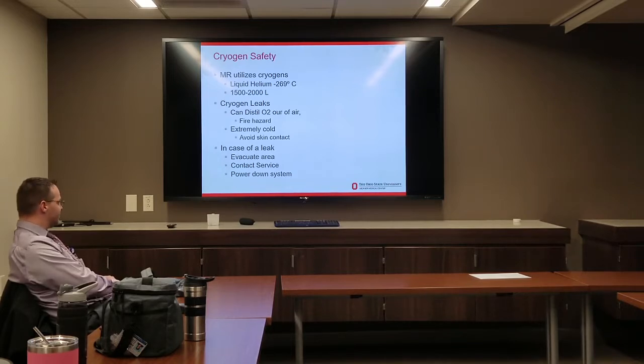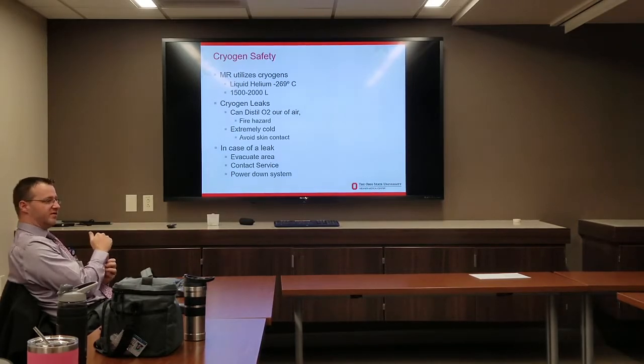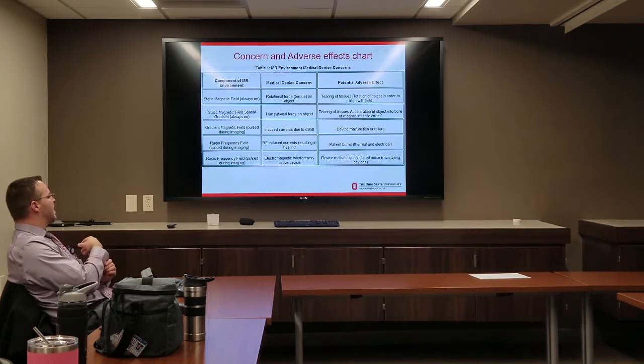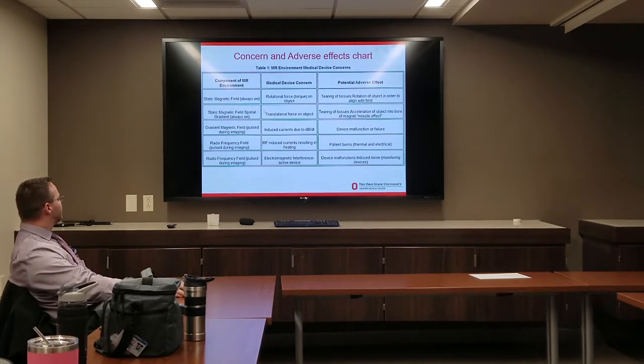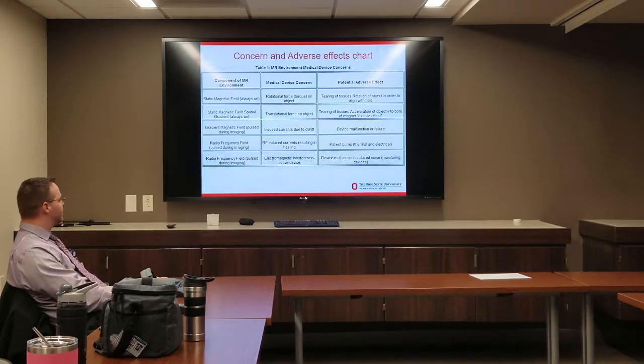Cryogens are also a safety concern — they are extremely cold, and the primary concern is from cryogen leaks, as they can distill O2 out of the air creating a fire hazard. Avoid skin contact if you ever find a cryogen leak. In case of any leak, evacuate the area, contact service, and power down your system. The hazard chart summarizes static field concerns (rotational and translational forces) alongside other MR hazards — a useful reference that will be available in the PowerPoint slides.